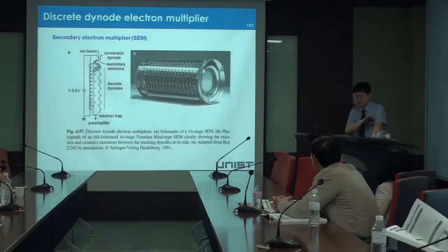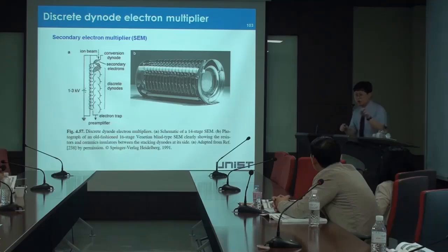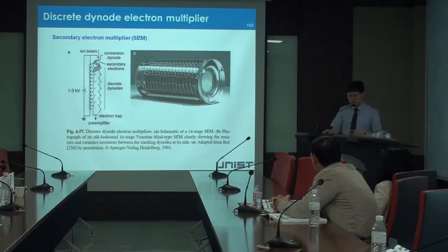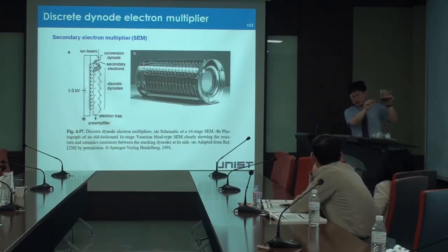So after passing through the mass analyzers, our ions enter into the detector. This is an electron multiplier. A small amount of ions enter into the detector, and this ion signal should be converted into an electric signal, so it makes many electrons for data recording. Consider that in this sample, we make a very small amount of final extract, and among it only 1 or 2 microliters enter into the GC.